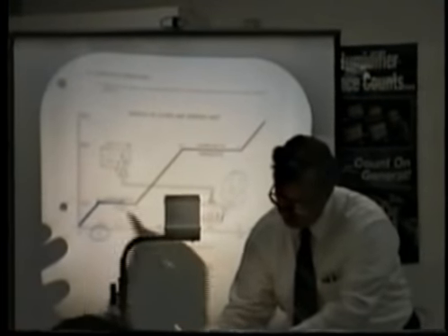Here we go. Are you getting ready in that? Okay, here we go. So if I go from a pound of 32 degree ice and warm it up to 32 degree water, how many BTUs did it take to do that? And the answer is 144. Wow. 144 BTUs to change the state. No change in temperature.